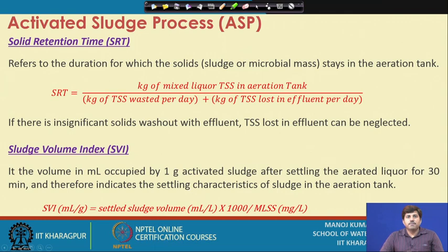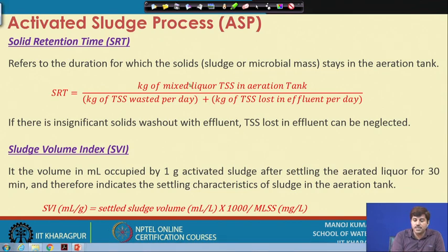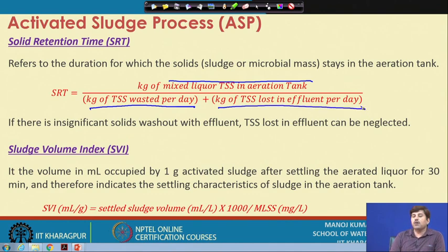Now, there are a few other terms, solid retention time, which is the SRT. This refers to the duration for which the solids, which is primarily sludge or microbial mass we are talking about, stay in the aeration tank. So, this SRT typically is the kg of the mixed liquor total suspended solids in the aeration tank, so how much total solids are present in the tank at any given point of time, divided by the kg of the total solids wastage per day plus kg of the total solids lost in the effluent.